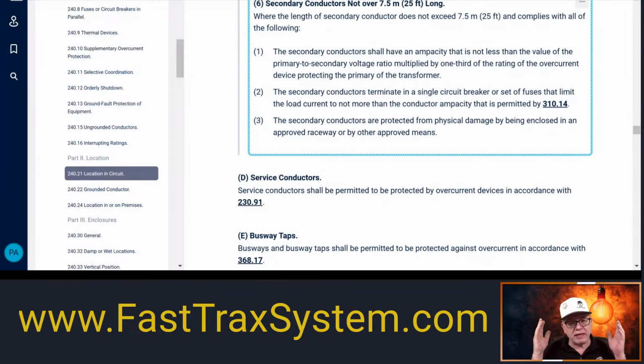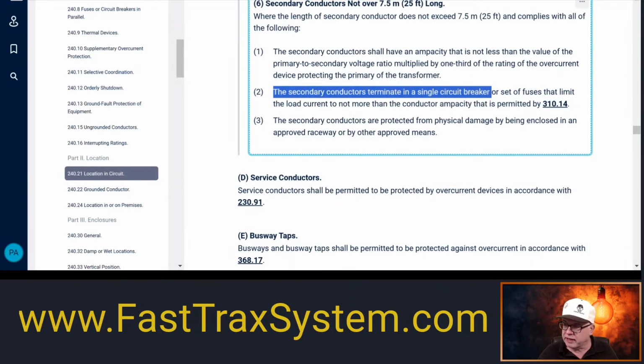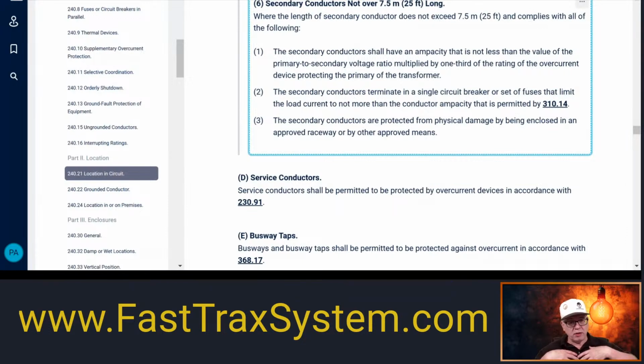Probably going to be larger than that, depending on the load that we're trying to serve. We get it. This is minimum rules. And as the secondary conductors, they have to terminate into a circuit breaker. And again, if the load of that panel that we're supplying is a 200 amp panel, and our transformer can handle that load, then we're terminating into a circuit breaker that's 200 amps.